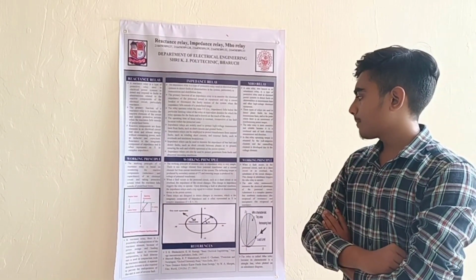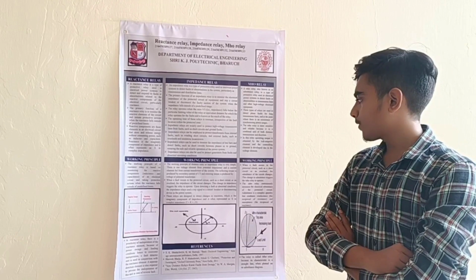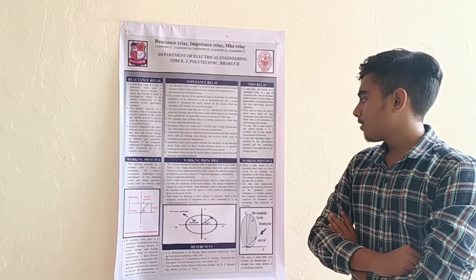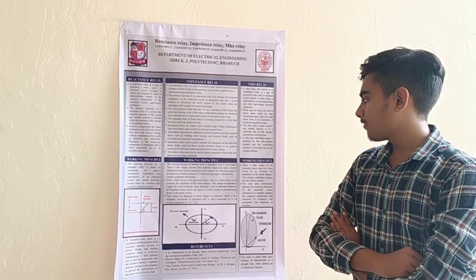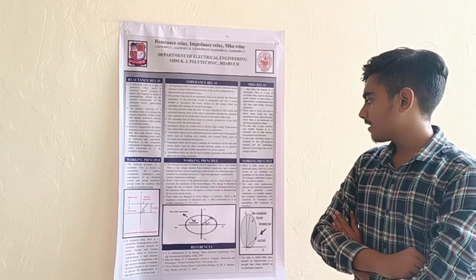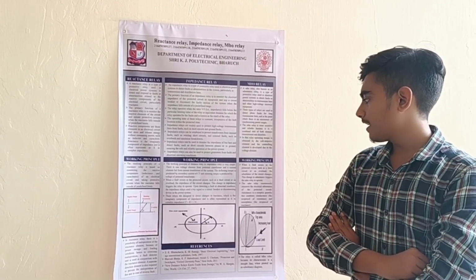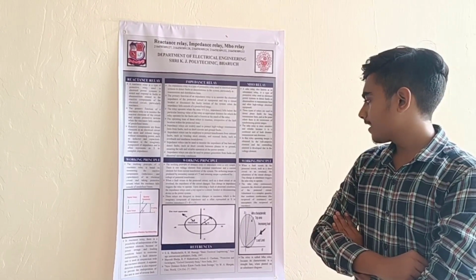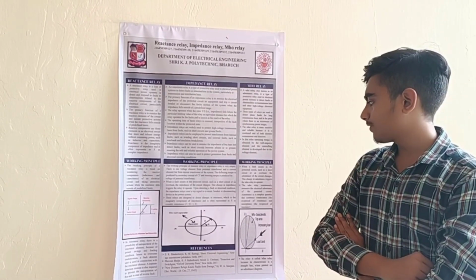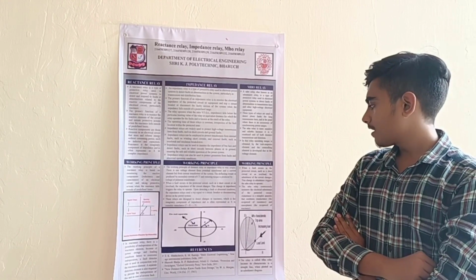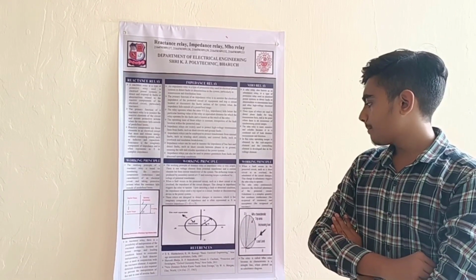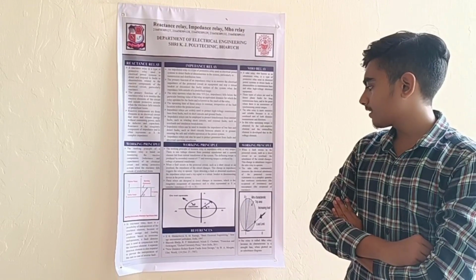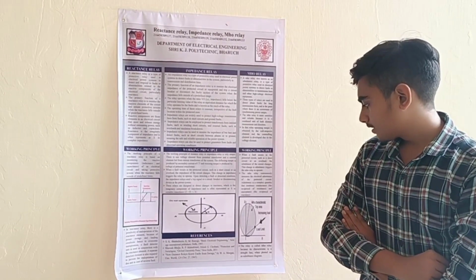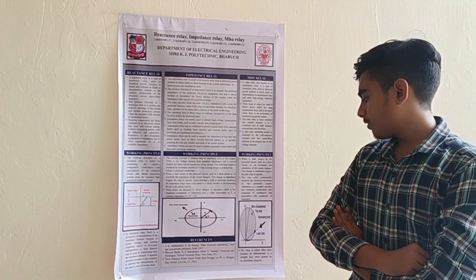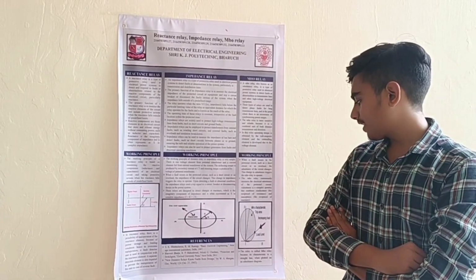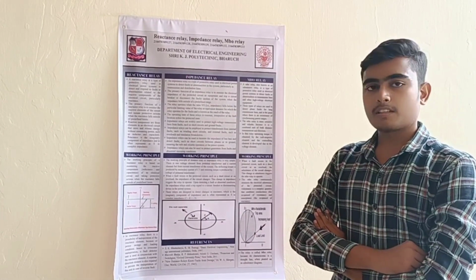Mho relay working principle. When a fault occurs in the protected circuit such as a short circuit or an overload, the admittance of the circuit changes. This change in admittance triggers the Mho relay to operate. The Mho relay continuously measures the electrical admittance of the protected circuit. Admittance is a complex quantity that combines conductance and susceptance. The relay is called Mho relay because its characteristic is a straight line when plotted on admittance.